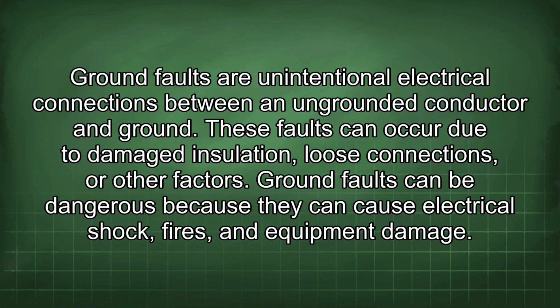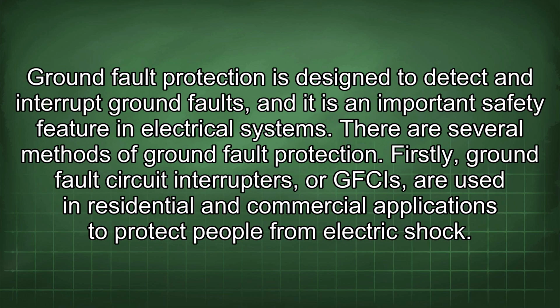personnel. Ground faults are unintentional electrical connections between an ungrounded conductor and ground. These faults can occur due to damaged insulation, loose connections, or other factors. Ground faults can be dangerous because they can cause electrical shock, fires, and equipment damage. Ground fault protection is designed to detect and interrupt ground faults, and it is an important safety feature in electrical systems. There are several methods of ground fault protection.